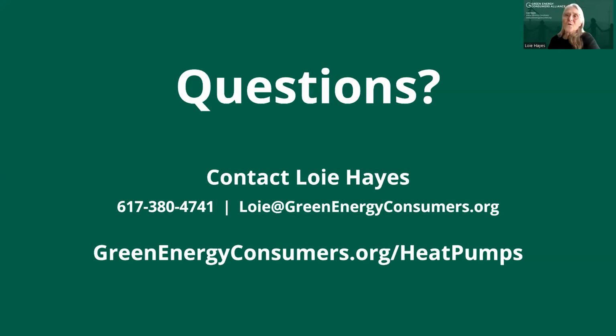So the cost of natural gas is very low. When you get down to colder temperatures, the efficiency of the heat pump - say it's working at 400% and it drops to 200%, then to 125% - the cost of natural gas, even though it's only 98% efficient, is still lower at that temperature than the electricity needed to operate the heat pump. That's why there are more partial systems, or why some people persist in wanting a partial system.